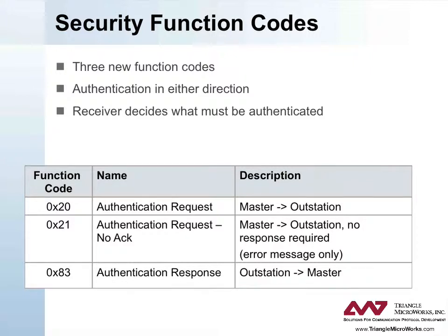Authentication can take place in either direction. Not only can an outstation verify that a control operation is authentic, but a master can also verify that the data it's receiving from the outstation is authentic. The specification includes a list of which items are mandatory to be authenticated. Controls must be authenticated, but it's optional whether data responses from the outstation are authenticated by the master. Each individual device has the choice of what must be authenticated for its proper operation.